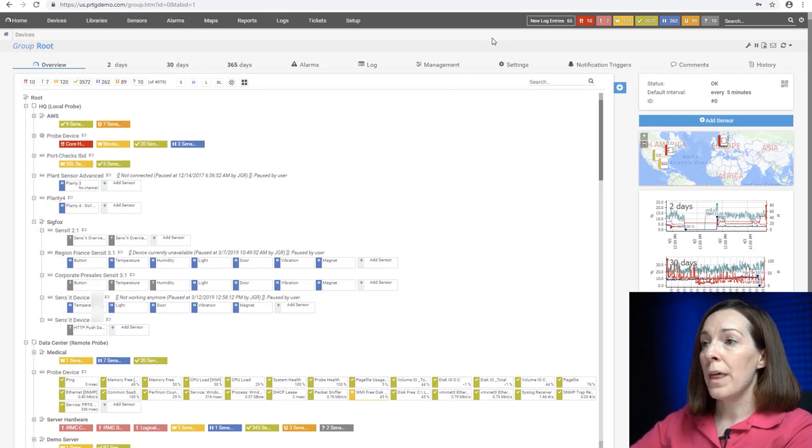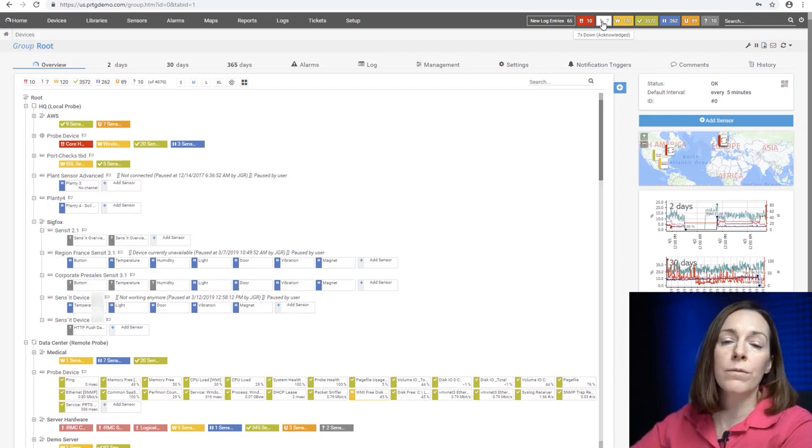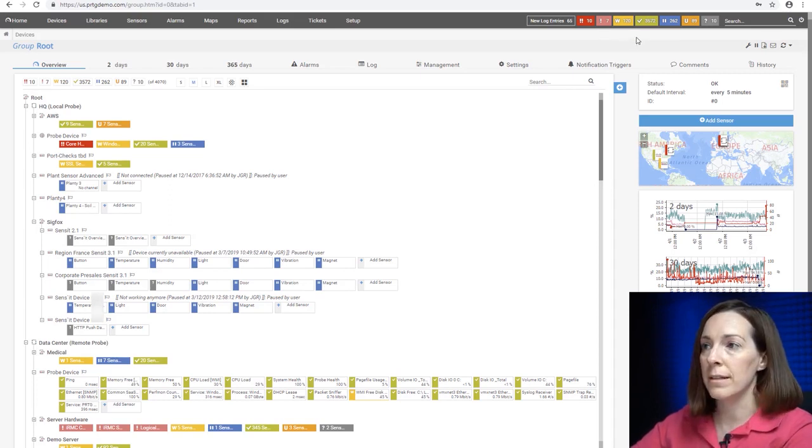All right, so then if you do go ahead and acknowledge that alarm, that's where you get the pink state, which is down acknowledged. So that's saying that the sensor is still down, but it's acknowledged, so therefore it will stop sending your notifications out, but it still will poll at its regular polling interval, and eventually once the condition changes, then the sensor will go into the up state again.